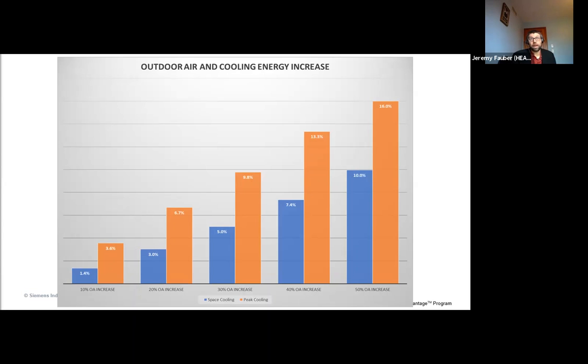In the case of a package rooftop unit where it already has a compressor, that's what you're really talking about: can that unit itself handle that percent increase, versus a central system like a chiller. With that sort of system, you have to look at not only can the chiller capacity handle this percent increase, but can the individual chilled water coils handle that? So you might have the capacity at the chiller because of diversity and how that chiller was sized, but you wouldn't have the capacity at the coil to deal with those increases.